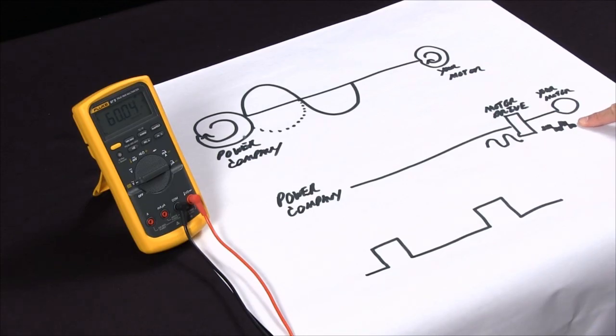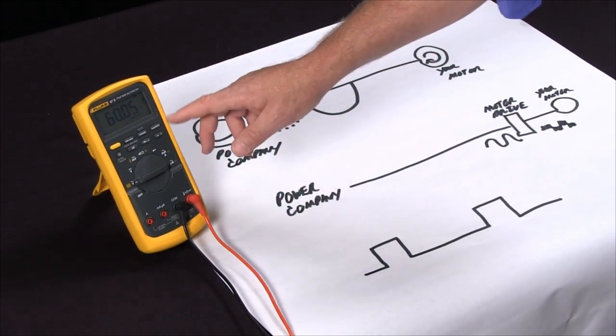So you can see if the motor is truly at full speed at 60 Hertz, half speed at 30 Hertz, quarter speed at 15 Hertz. That's a useful addition that we've put into all our new Fluke 87 multimeters with the Hertz and duty cycle function.